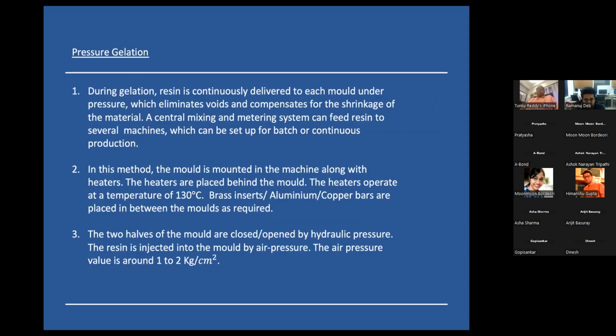Now pressure gelation is slightly different from gravity casting. Pressure gelation is used when you require batch production or continuous production. During pressure gelation, the resin is continuously delivered to every mold under pressure, and this helps in eliminating the voids. As I mentioned earlier, voids can decrease the performance of the component. In this method, the mold is mounted in the machine along with heaters. The heaters are placed behind the mold and they operate at a temperature of 130 degrees Celsius.